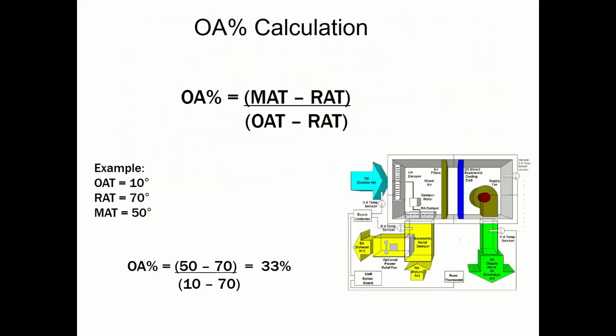If you want to see how much outside air you're bringing in, I don't remember if I showed this to you guys last week or not. I think I did. But on a non-mild day, meaning on a cold day or a hot day, I can measure the temperature of the outside air, measure the temperature of the return air coming back to the unit, and then measure the mixed air. And then using this simple formula, I can figure out how much air is coming from the outside and how much is coming from the return. Right? So this is available to you if you want to try it this way. It's an easy way to measure the difference there.